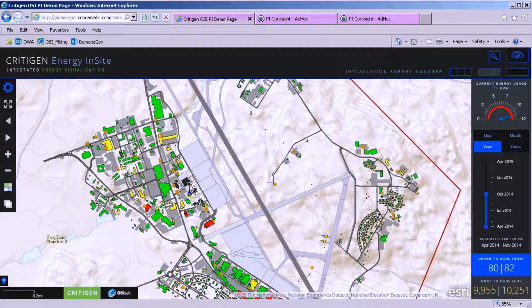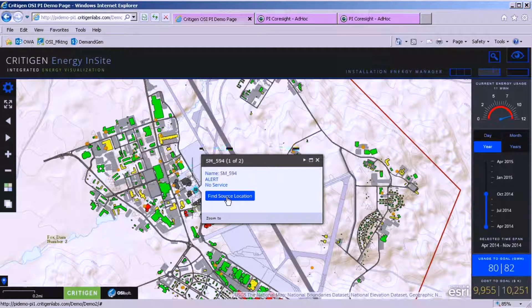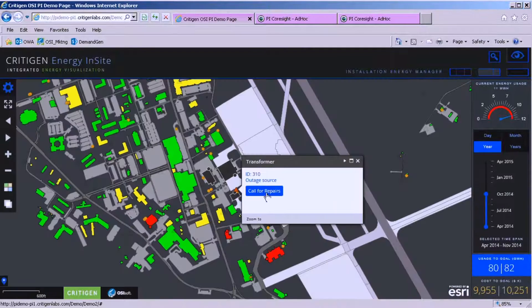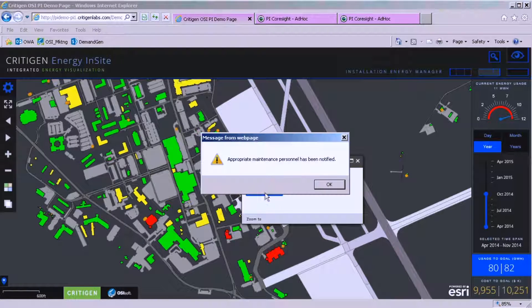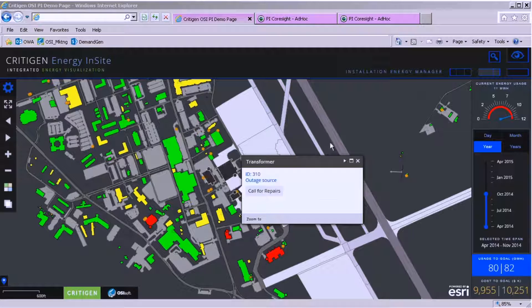I can interrogate the map — I have a meter here with no service, and another meter with no service. I think those are on one transformer, so I select a button that says 'find source location.' Now we understand that transformer 310 has gone out. I select 'call for repairs,' which goes out through a work manager such as SAP Work Manager, and the appropriate maintenance personnel have been notified. I can take a break and go get my coffee.